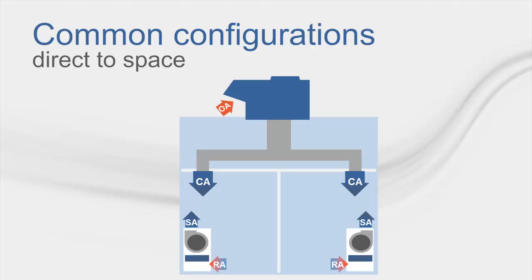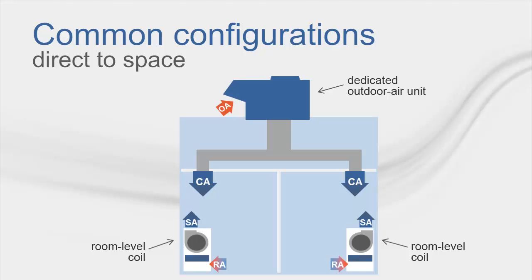To demonstrate how a dedicated outdoor air unit can be applied to a system, let's consider an air-side system with a room-level coil such as a fan coil. The DOA, which can be found on the roof in the schematic, meets the outdoor air requirements by treating the outdoor air for all the rooms in the system. The conditioned air is then supplied directly to the rooms, and the fan coils controlled by room thermostats satisfy the remaining cooling and heating loads in each room.